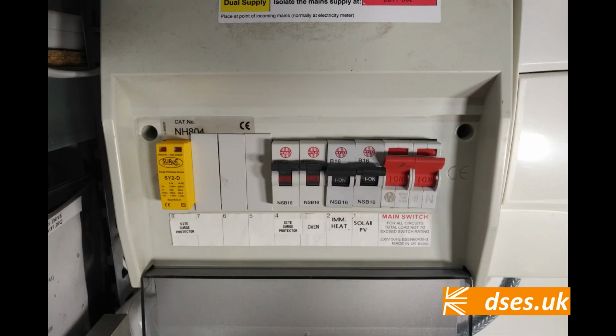This second DB is an overrun, as new circuits have gone in since DB1 was installed. A wired smoke alarm circuit, the solar PV system, which I installed myself in 2014, the surge protector I installed in 2018, a 20 amp circuit for electric heating, which serves various radiators and underfloor heating mats upstairs, and the immersion heater for hot water, which, although an original circuit in the house, was never connected to the 16th edition board or to the Wylex replacement back in 2012. It only got reconnected in 2014 when my gas system was decommissioned.